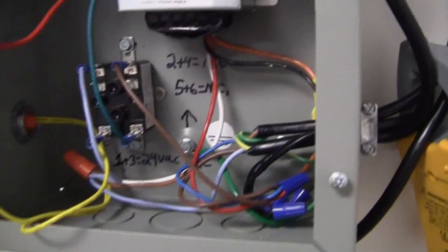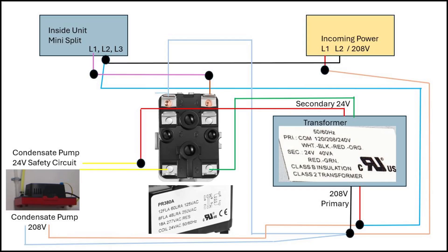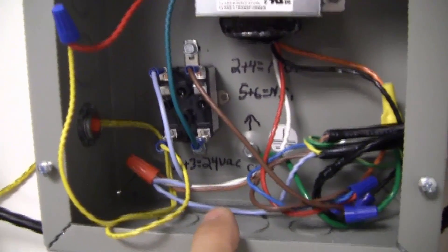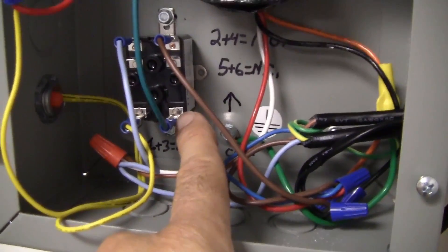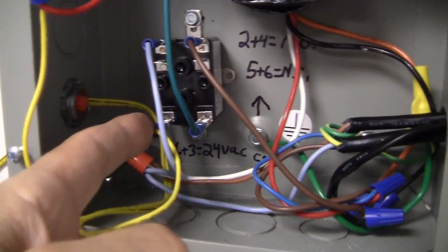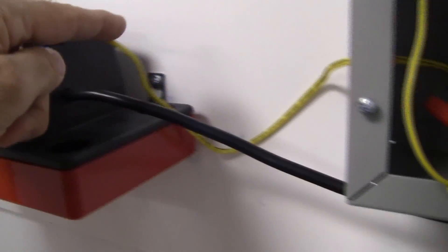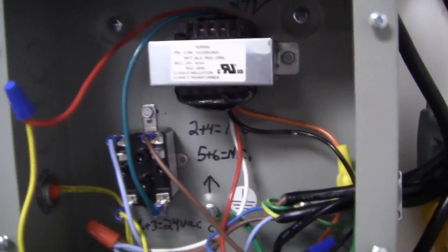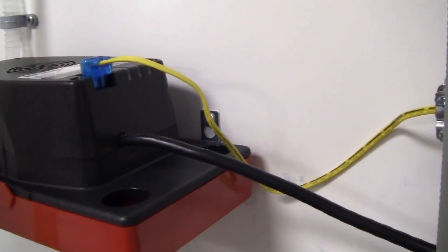Here's the actual wiring diagram. On your secondary your 24 volts for your transformer the green wire is coming and landing on one side of the 24 volt coil then we come out of there with a yellow wire and then that comes over and it goes to one side of the safety circuit on our condensate pump. On the other side of the safety circuit it comes up and it lands on the other side of the 24 volts for the transformer. So there's your 24 volts and here's your interruption right here when we have it when you reach that high level because the pump's not working.